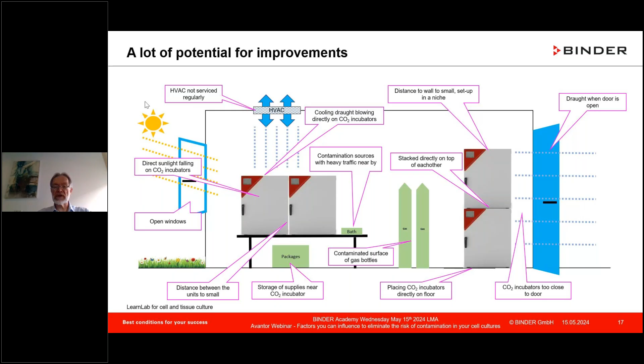Store supplies outside of the lab. Keep the doors closed if open, very, very quickly. Eliminate any kind of critical niches, which you're doing by placing it away from the door. The gas bottles, position them outside, having tubes leading then into the lab and connecting to the CO2 incubators.